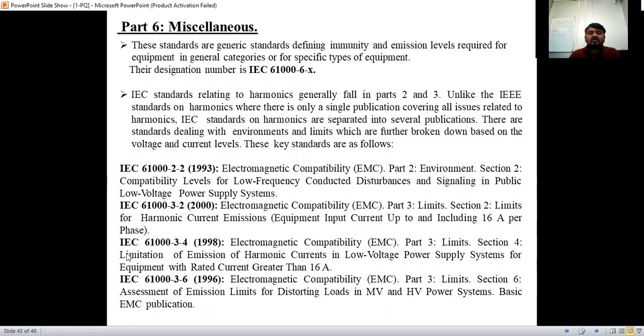Similarly, IEC 61000-3-4: part 3, section 4. We discussed section 2; now section 4 gives different standards, implemented in 1998. Section 4 is called limitation of emission of harmonic currents in low voltage power supply for equipment with rated current greater than 16 amperes. So for rated current greater than 16 amperes in low voltage power supply, this section 4 applies to harmonic current emissions.